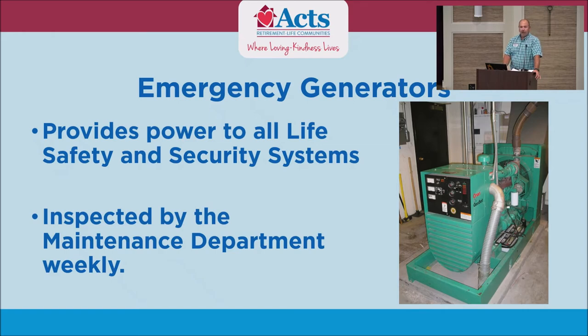Every month we do a load test. We have nine transfer switches on the property. Every month we are required to start the generator by a different transfer switch, so in the event of a power outage we know that transfer switch was sending the signal to crank the generator. We have had times where A building, the clubhouse, and health care building had power with no problems, but we've had problems in the feeder coming into B building — so the generator was running but just servicing B building at that time.